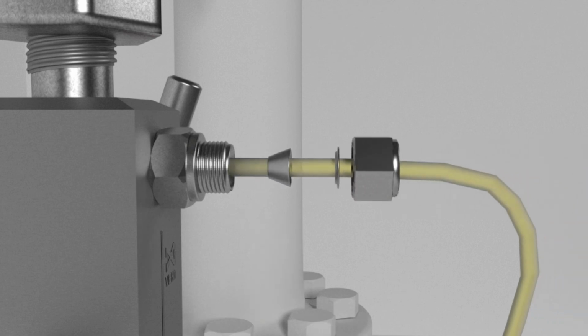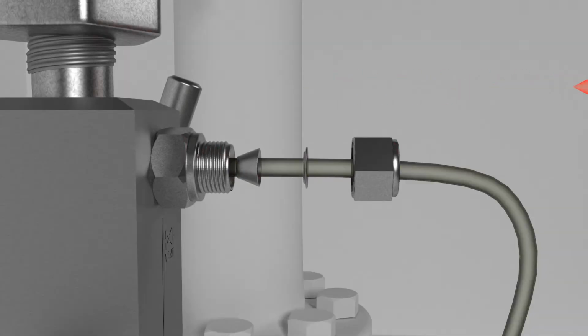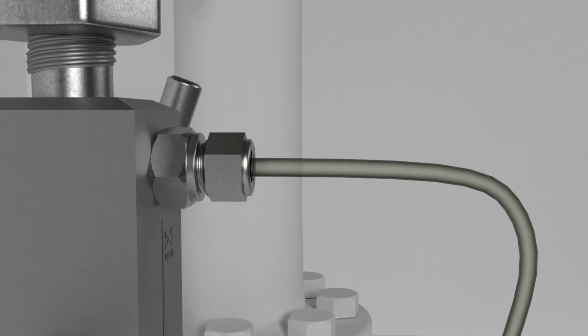Make sure you have both ferrules in place and that they are facing the right direction. The ferrules should always be pointed towards the connection, and the cone goes first, meaning that the smaller end of the coned ferrule is facing the manifold and the smaller inner ring on the flat ferrule faces the cone. You can see the tubing connection videos for further instructions on this topic.